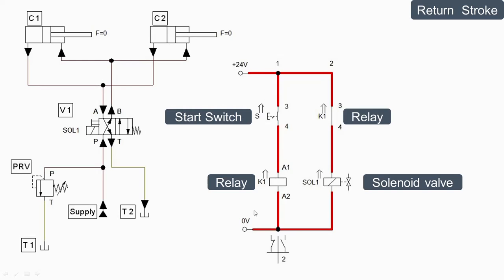This simple electronic circuit consists of a source of 0 volt and 24 volt. When switch S is closed, relay K1 gets energized and operates solenoid valve SOL1 — the coil of the solenoid valve. SOL1 energized corresponds to the left envelope mode, and we will get the left envelope mode in the direction control valve.